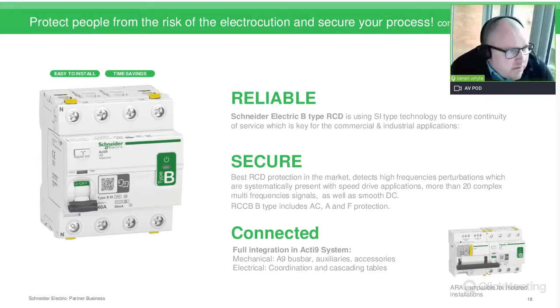So protect people from the risk of electrocution and secure your process. So Schneider RCDs, reliable, secure and connected. We also do a range that has outputs, so you can monitor the status of the RCD. So if you look at a commercial environment, that can be linked into a BMS or a process control system to identify the status of your system. We also have, as we say, the full range, the AC, the A, the F, and the B.